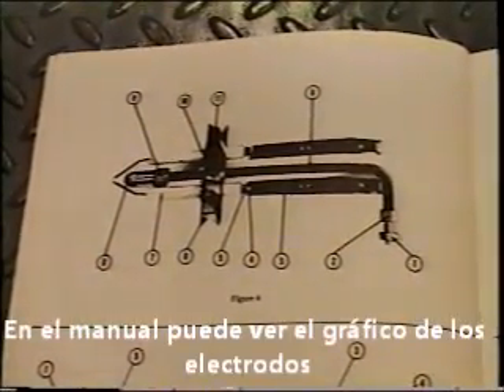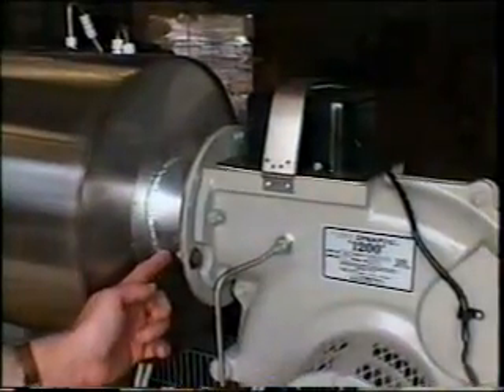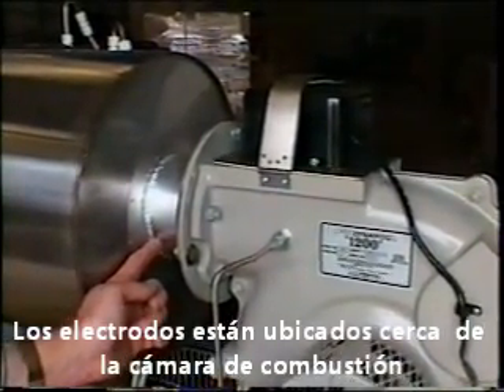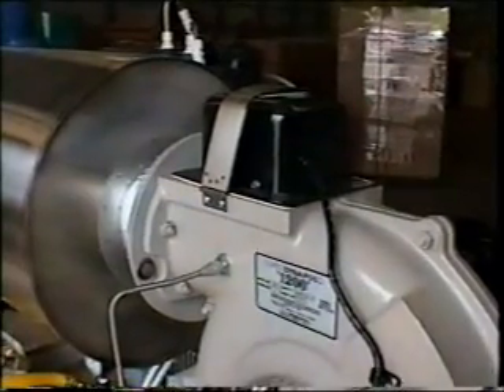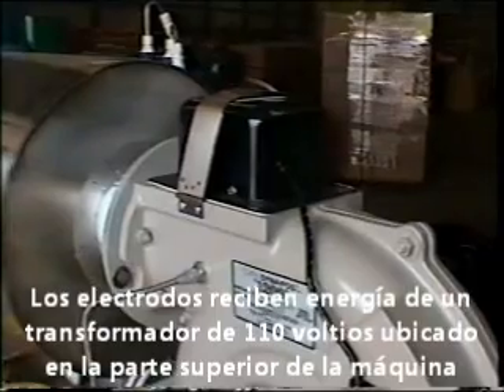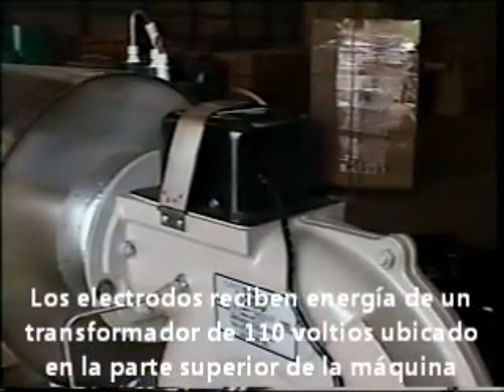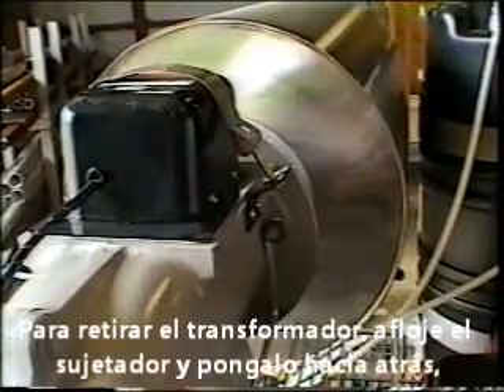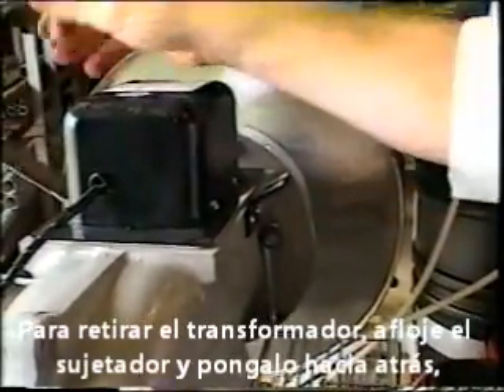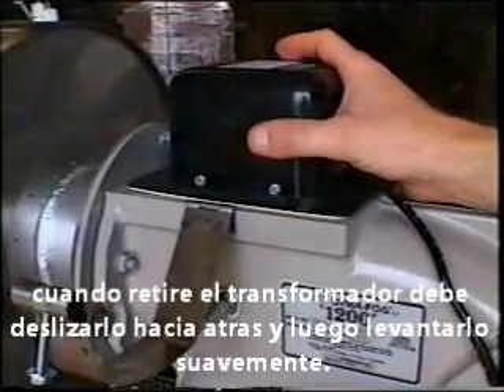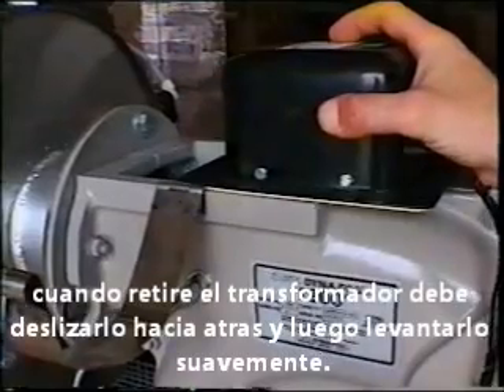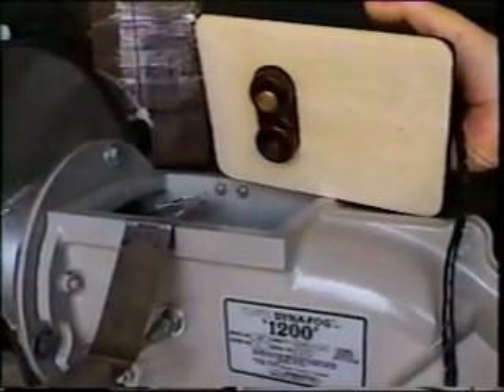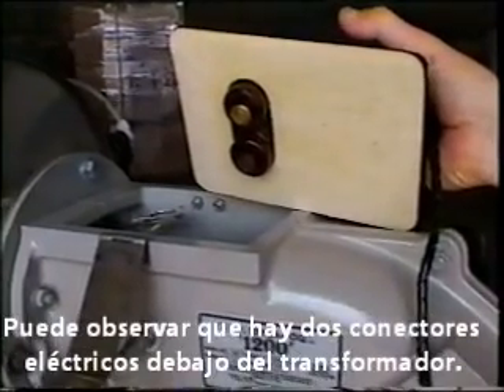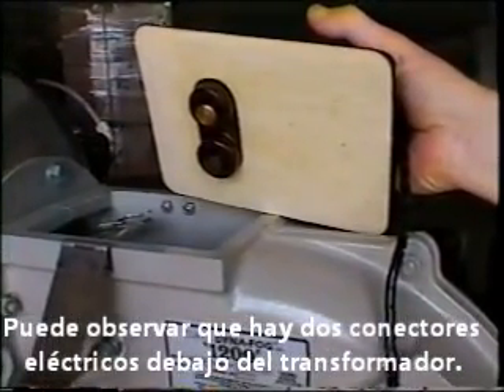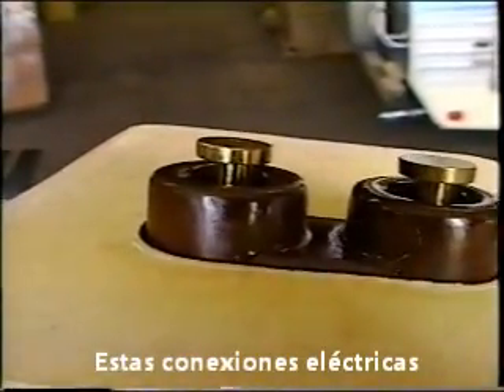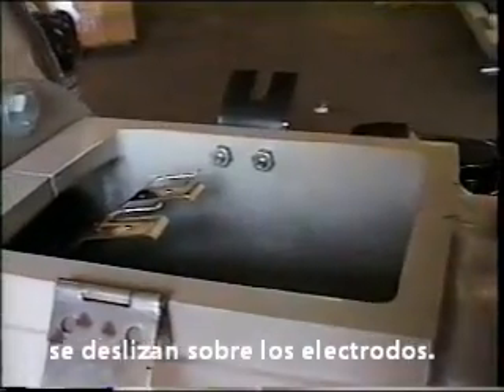In the manual, you will see a photo of the electrode. The electrodes are located near the end of the combustion chamber. The electrodes receive their energy from the 110 volt transformer located on top of the machine. To remove the transformer, unloosen the bolt and flip the clamp out of the way. When removing the transformer, you must slide the transformer back and then in an up motion. You will observe that there are 2 electrical connectors on the bottom of the transformer. These electrical connections will slide in and out of the electrodes.